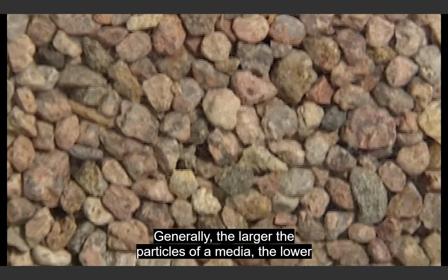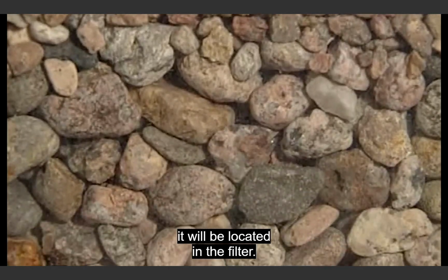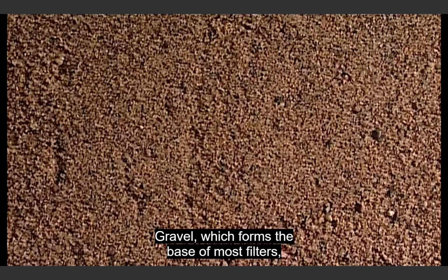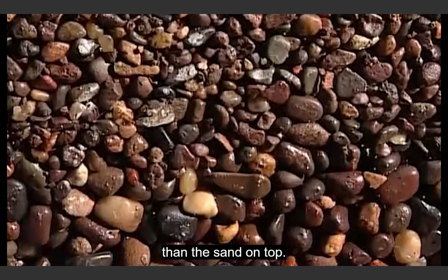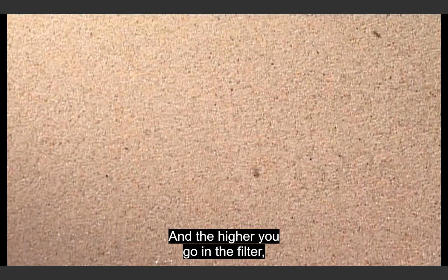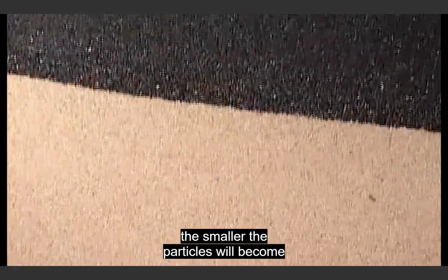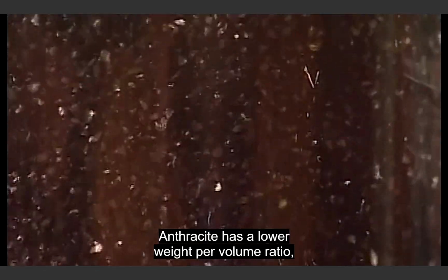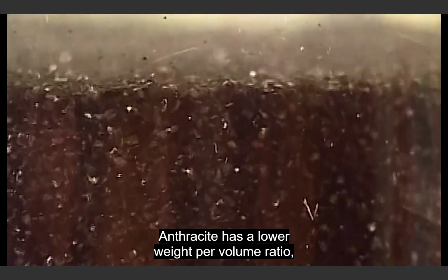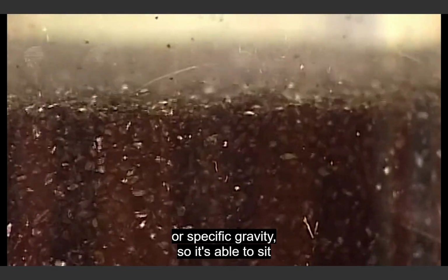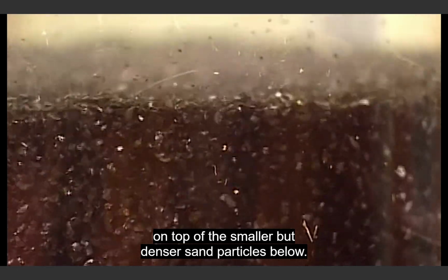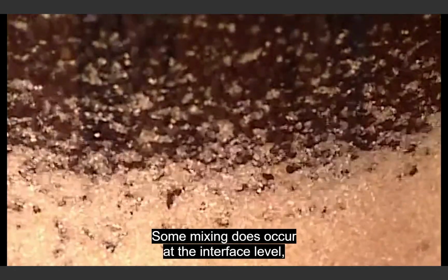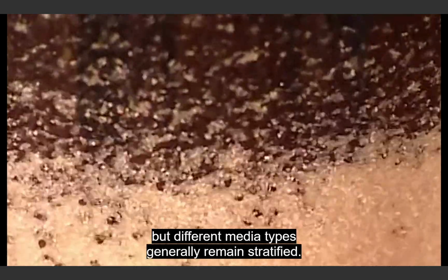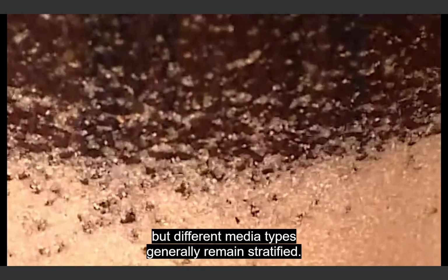Generally, the larger the particles of a media, the lower it will be located in the filter. Gravel, which forms the base of most filters, stays at the bottom because it is larger and heavier than the sand on top. And the higher you go in the filter, the smaller the particles will become, with the exception of anthracite, which is found at the top. Anthracite has a lower weight per volume ratio, or specific gravity, so it's able to sit on top of the smaller but denser sand particles below. Some mixing does occur at the interface level, but different media types generally remain stratified.